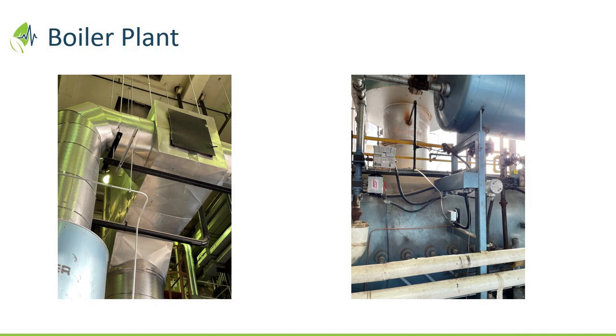So as you see heat exchange start to decline, because you've got scale or soot, you're not taking the heat energy out of the flue and it's going up the stack. So your stack starts to elevate in temperature. These have lockouts on temperature control, as many boilers will. But these days we've got the technology where you can track that and get alerts, like, I'm drifting 50 degrees over the last 3 weeks, something's going on. And you can get ahead of that.